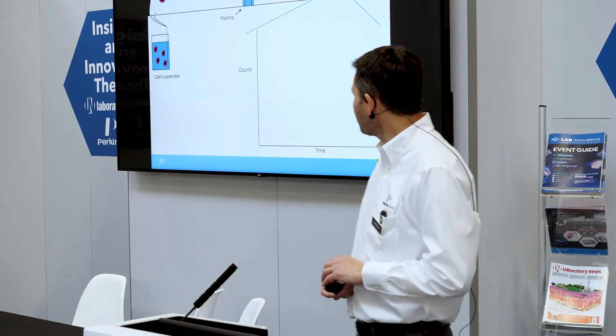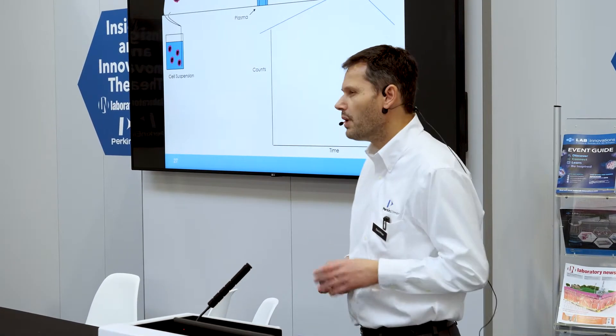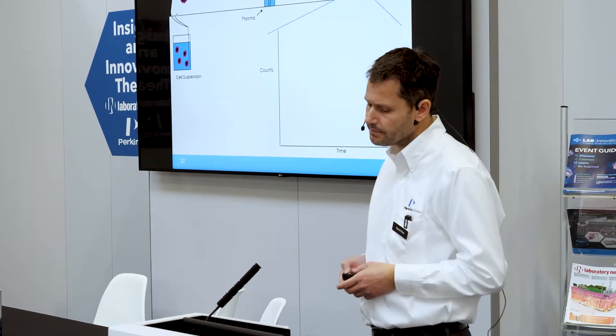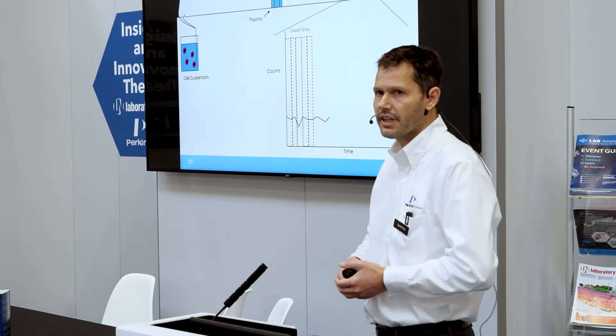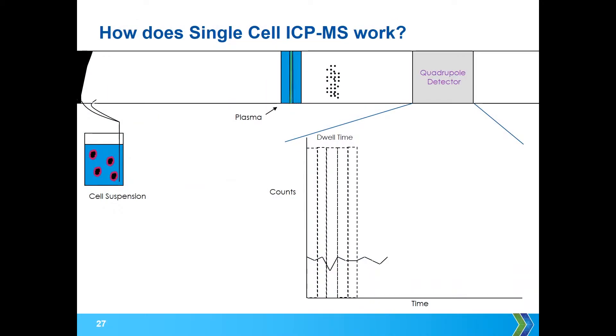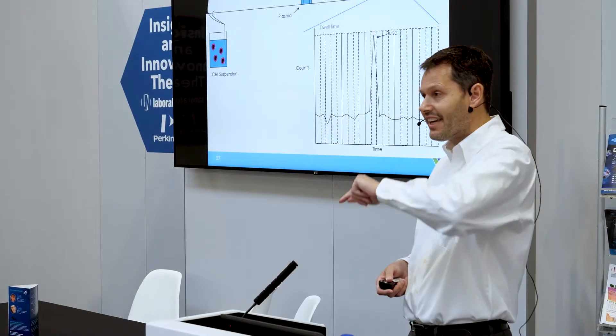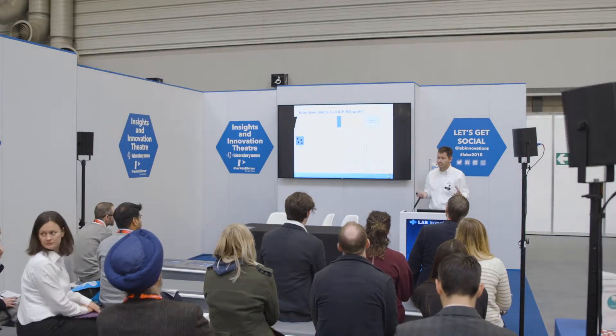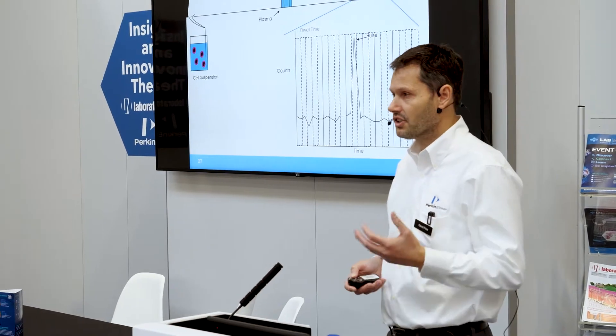This is the most unusual ICP-MS you'll ever see. In single-cell ICP-MS, we have a cell suspension — typically around 50,000 to 100,000 cells per milliliter, which is relatively low concentration. We take those into the plasma and ionize them, creating a little ion cloud. Taking platinum as an example, we generate platinum ions, see them as a little cluster going through, and detect that. We have very short dwell times to track as the signal hits the detector — it goes up, we track it, it comes back down. We measure the area of that peak: a lot of platinum in a cell gives a big peak; a small amount gives a small one. We keep throwing in lots of cells and get lots of information.